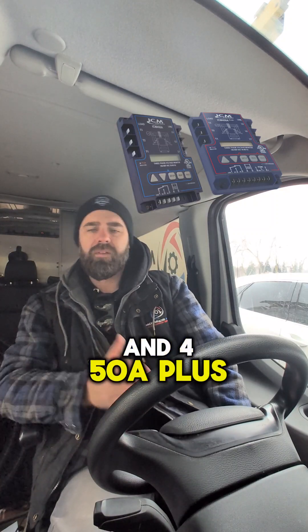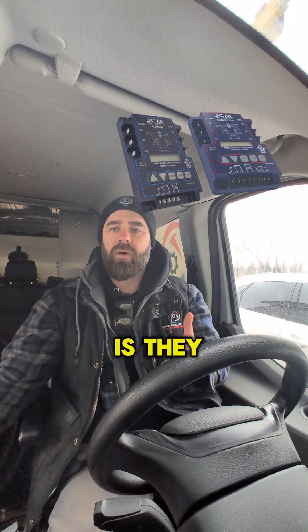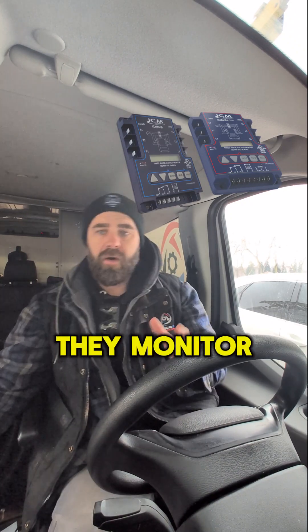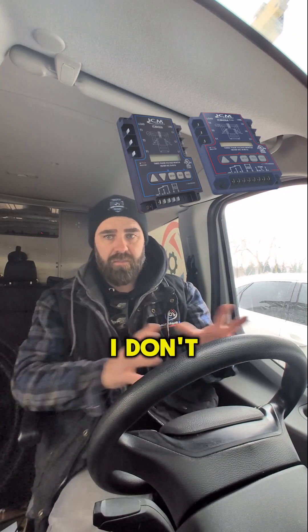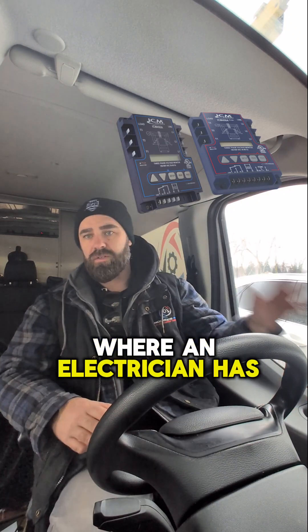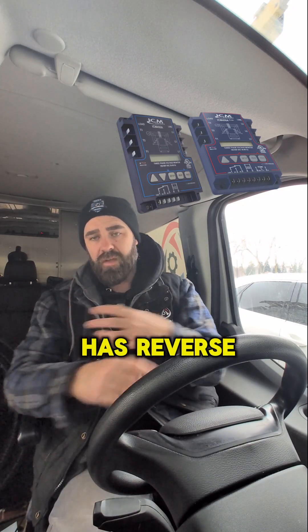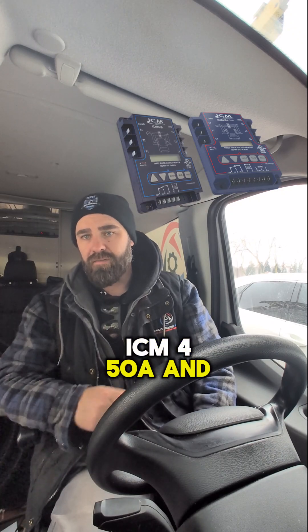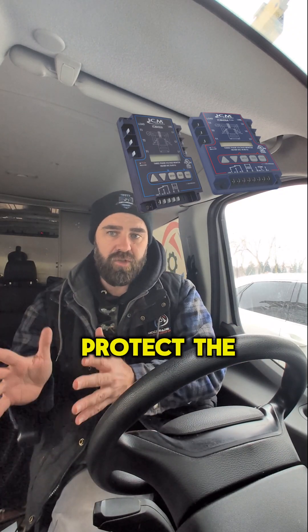These ones here are the ICM450A and 450A+, and I got some notes written down here. What they do is they monitor high and low voltage, voltage imbalance, phase loss, and also phase reversal. I don't know how many times I've been into a building where an electrician has done something and that unit now has reverse phase and everything's running backwards. So that's what the ICM450A and 450A+ does — it monitors all of that to protect the machine.